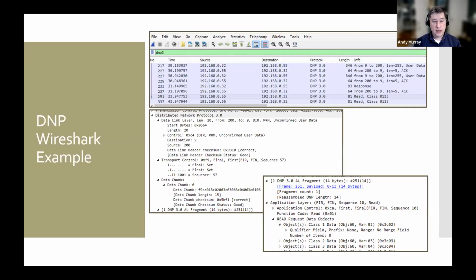I just want to show quickly a DNP Wireshark example. Like I mentioned, it's a clear text protocol. Wireshark has the ability to interpret DNP, Modbus, and a bunch of other protocols used in the industry. You can see here it'll break it down for you, showing exactly what's coming across, even which bits were set. I use Wireshark a ton in the field, and you can also see where for cybersecurity there could be a lot of pluses and minuses to having this ability so easily built in.